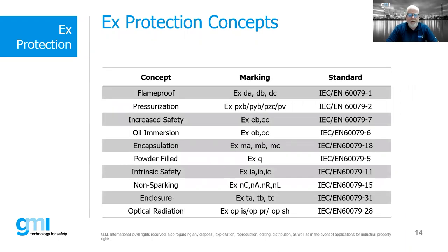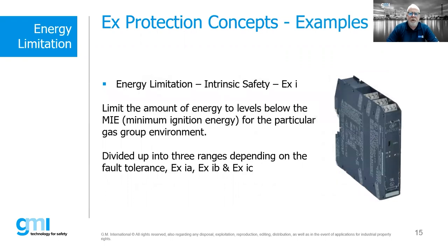The protection concepts include flame proof, now marked as EXDA, DB, or DC — the old EXD has been divided into three different concepts depending on gas group or zone. Intrinsic safety limits the amount of energy below the minimum ignition energy for the particular gas group environment. It's divided into three ranges: EXIA (double fault tolerant), EXIB (single fault tolerant), and EXIC (no fault tolerance). They all operate in the same fashion — limiting the amount of energy that could be released into the hazardous atmosphere.